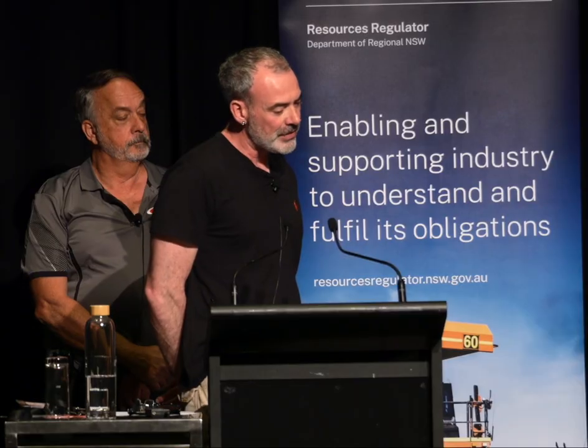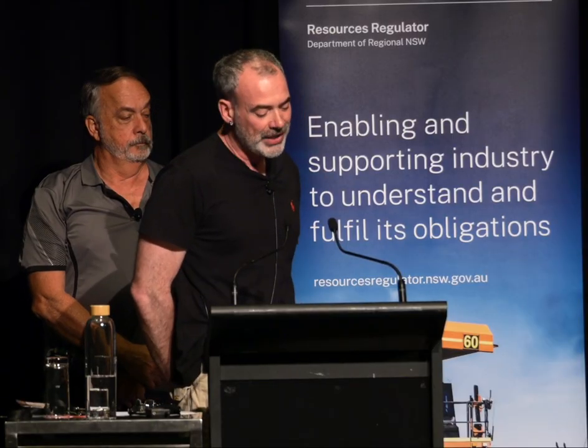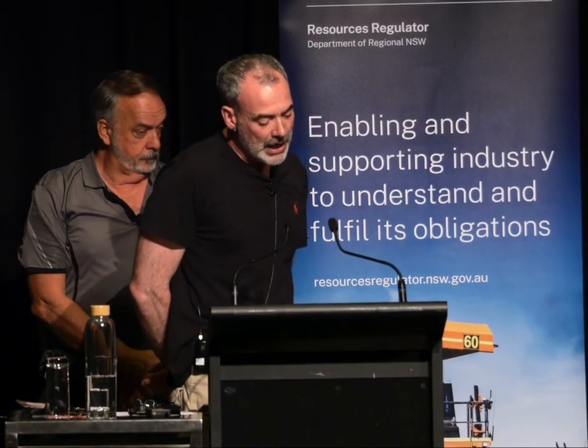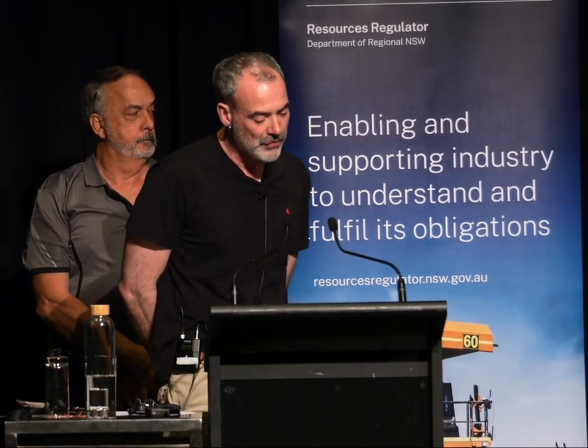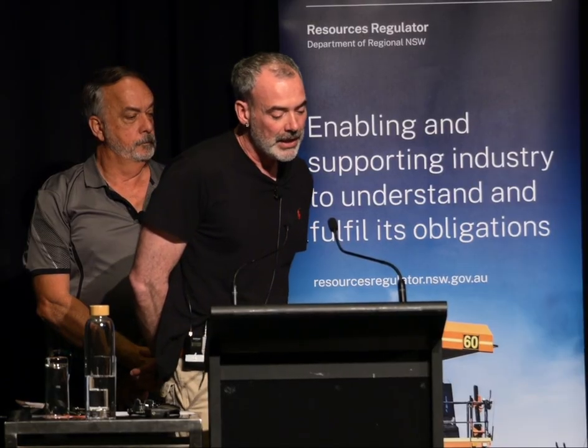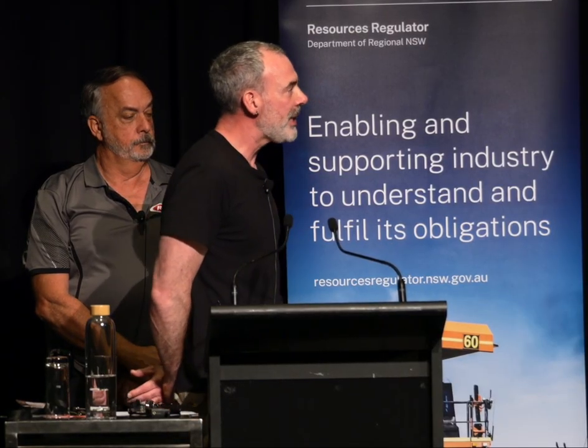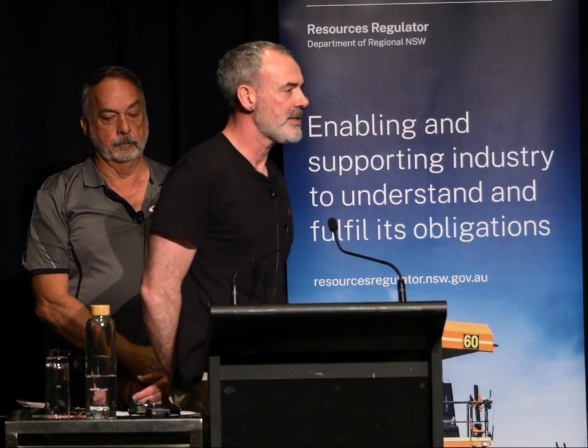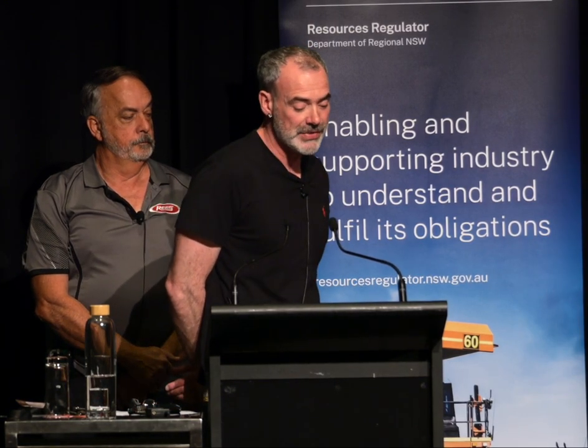IEEE C57.12 defines a 4-letter character code, such as ONAN or KNAN. The character code describes the cooling attributes of the transformer, and the first letter, either O or K, refers to the main cooling medium, which is in contact with the windings. And a K-class fluid has a fire point above 300 degrees Celsius.